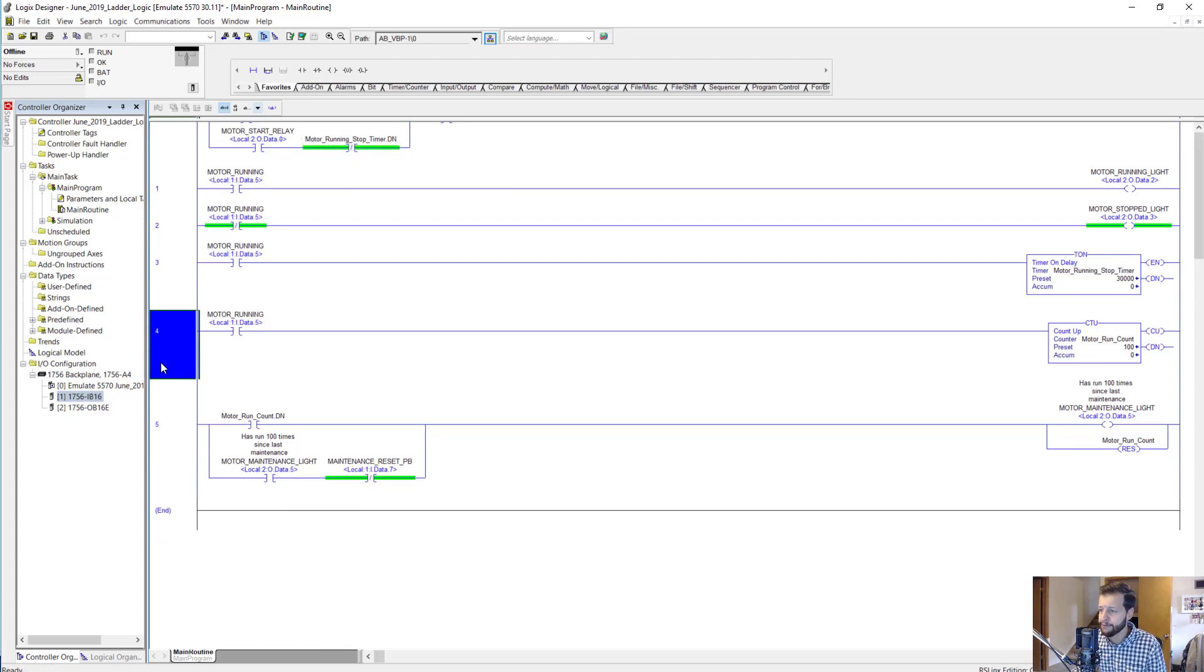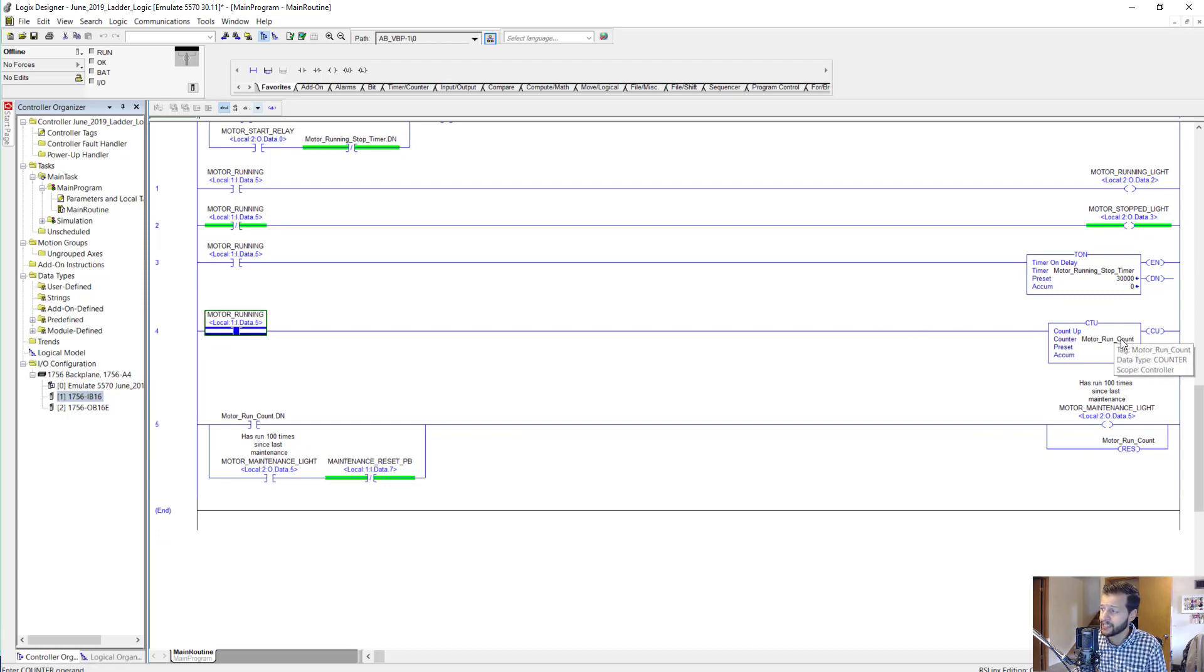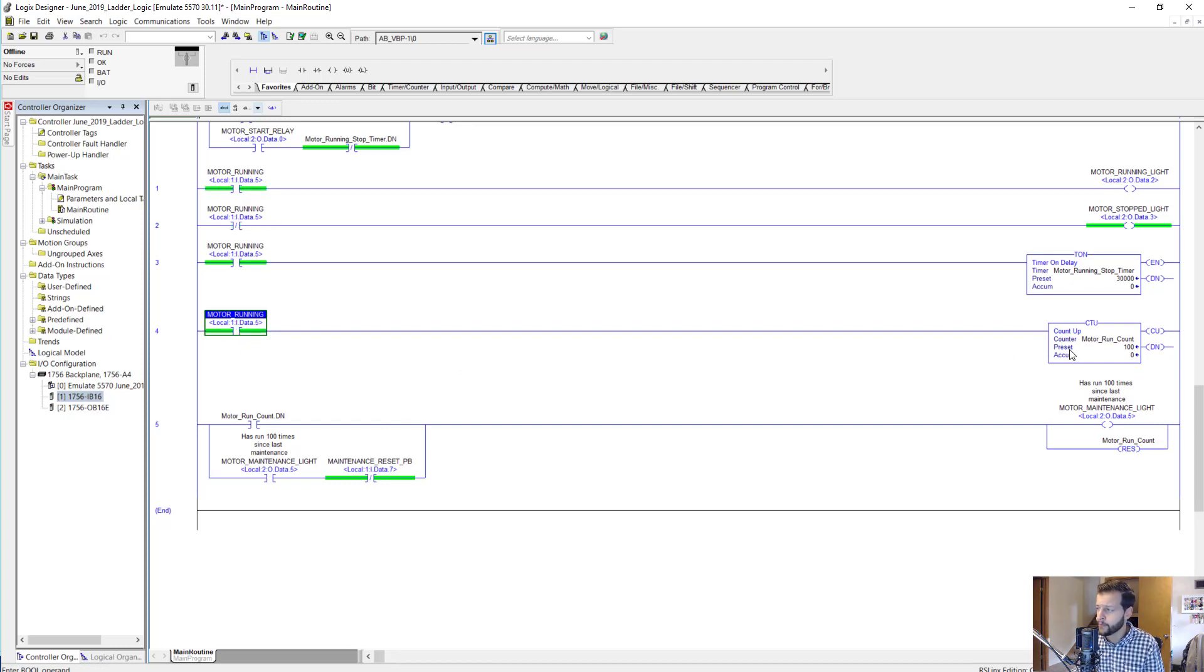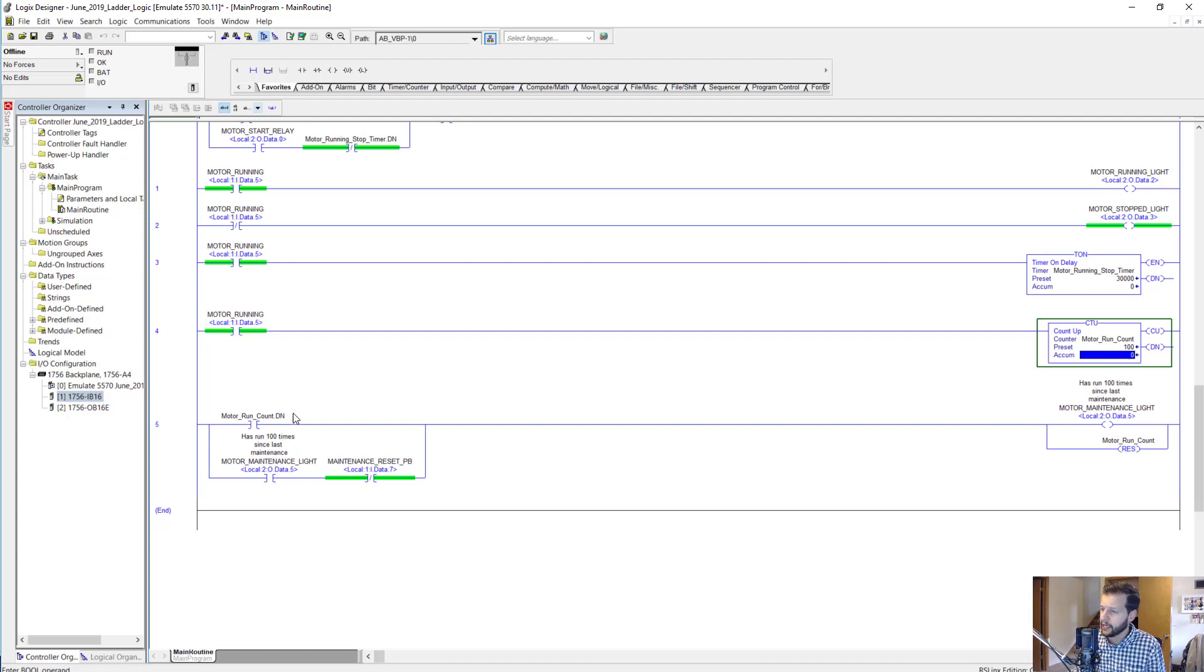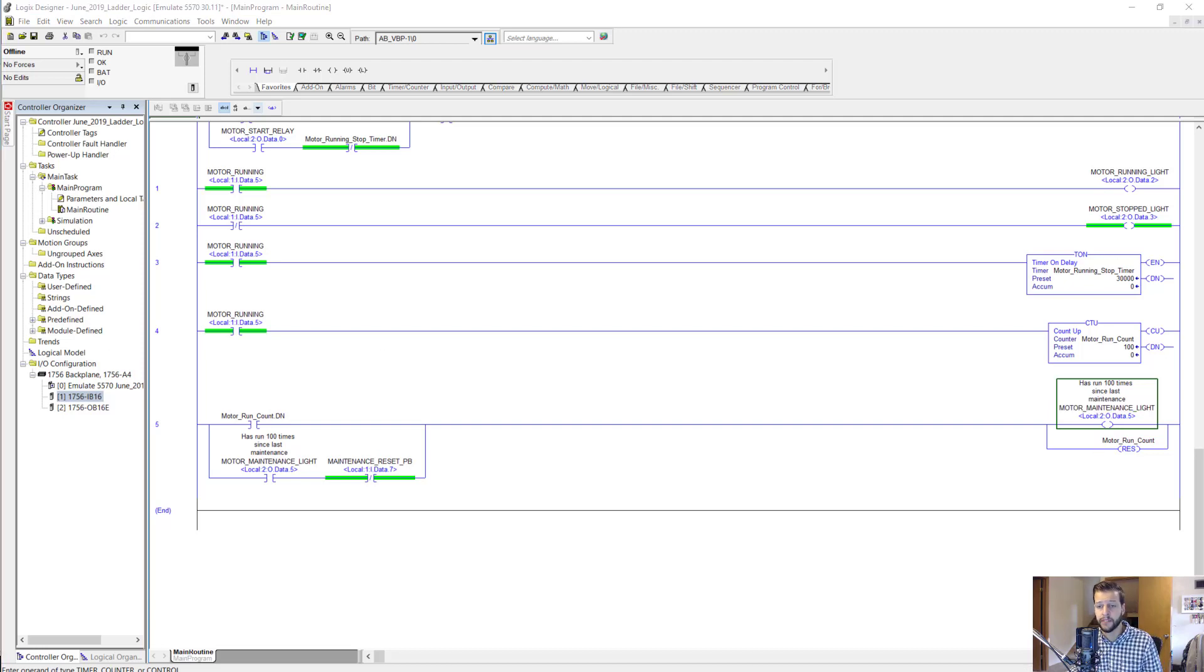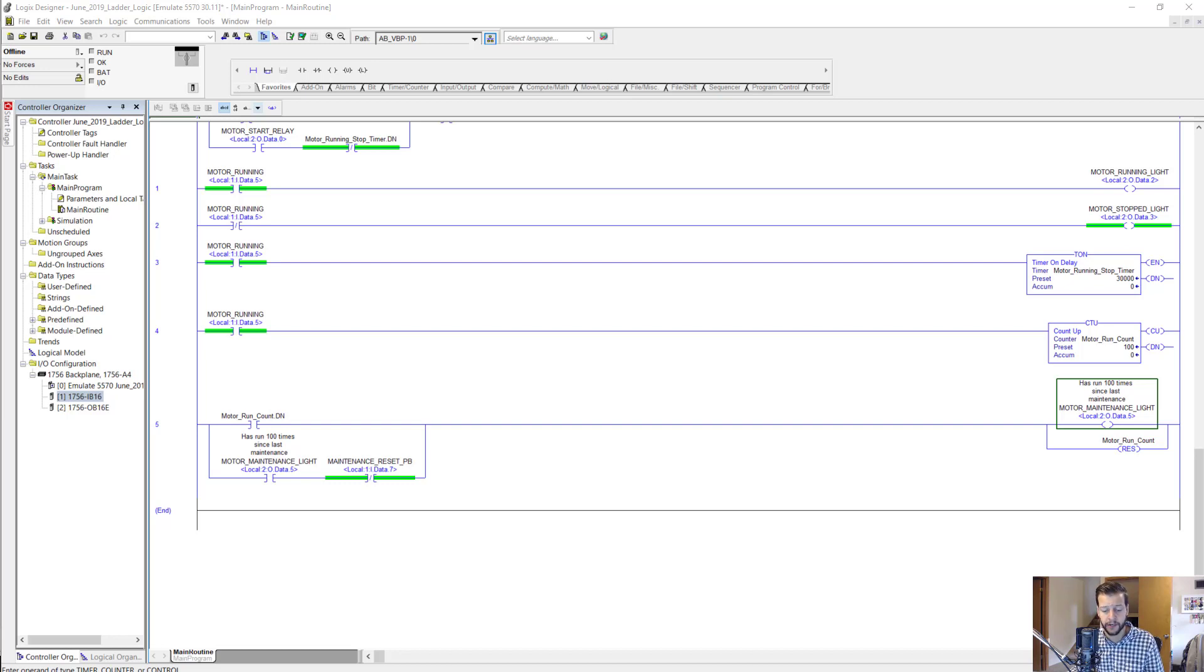Next we have a motor running bit driving the motor run count counter. This is a count-up counter, so anytime this pulses on—goes from off to on—this is going to count up one. Once it gets to a hundred, that's going to turn on the done bit for the counter, which will turn on a motor maintenance light. This would be a situation where the motor's run a hundred times and every time it's run a hundred times you want to make sure you do a maintenance check on it or something.